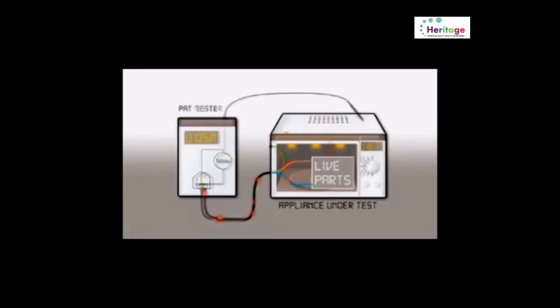When testing insulation on a Class 2 appliance, the test probe is connected to any exposed metal parts. If the exposed metal parts are insulated from live parts, a high insulation resistance measurement is obtained. If there is a breakdown in insulation between live parts and any exposed metal parts, a current will flow across the insulation and back to the PAT via the test probe. The measured insulation resistance is greatly reduced, indicative of an insulation fault.